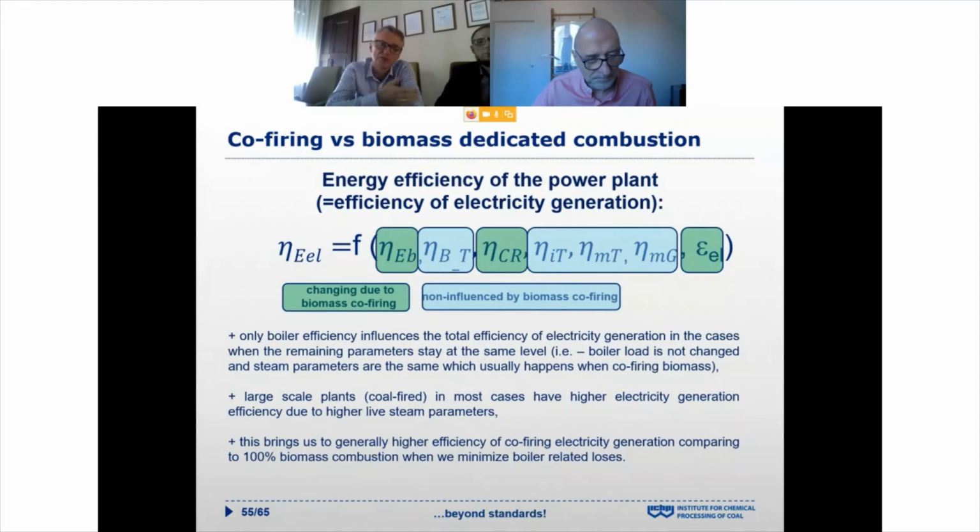As you remember from the previous slides, when we add the steam reheating to the basic steam cycle, we increase the total Clausius-Rankine efficiency due to the reheat. That's normal. We know it as engineers. It happens. But the assumption is the same, that we reheat the steam. The efficiency gain assumption is that we must reheat the steam to the same level as the live steam. But as you observed before, sometimes we cannot do that when we add the biomass to the base fuel.